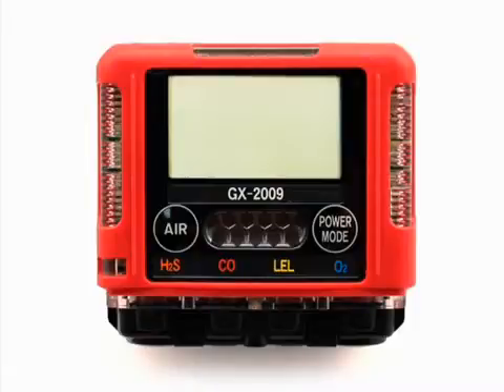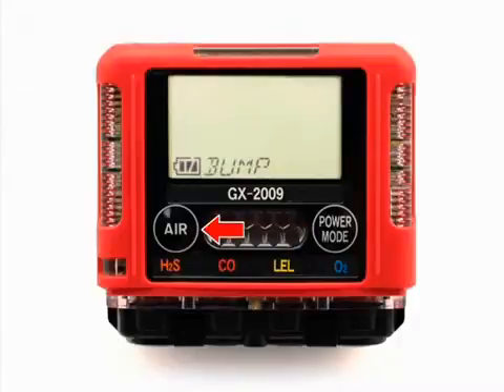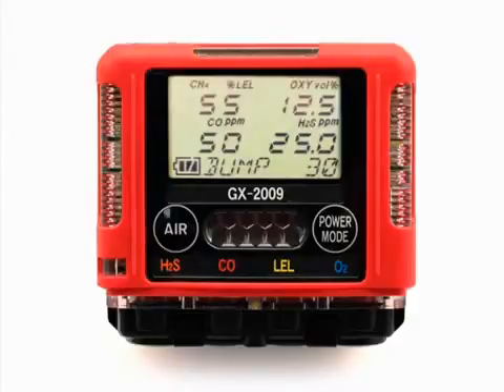To enter calibration mode, press and hold the air button, then press and hold the power mode button until you hear a beep, then release the buttons. Use the air button to move forward through calibration mode until bump is displayed. Press and release the power mode button to enter. The screen will display the gas concentrations that the GX 2009 expects you to use. These values are the same as the auto calibration values. If they are not correct, you must change them by entering the auto cal menu item in calibration mode.